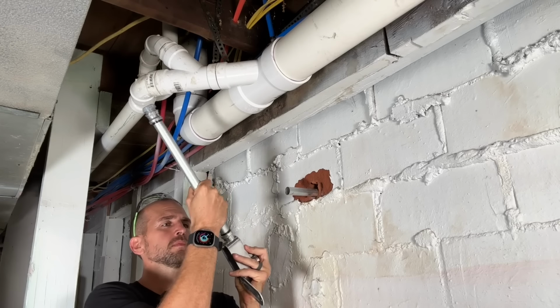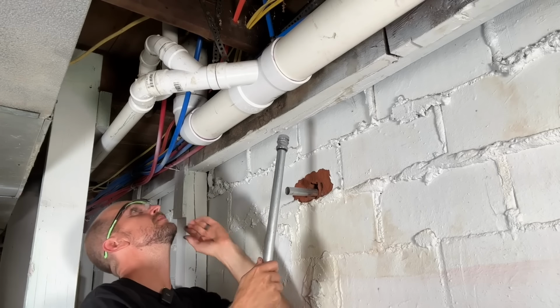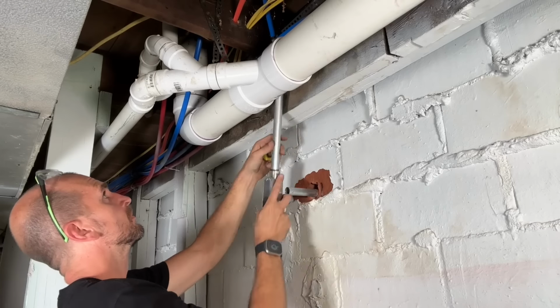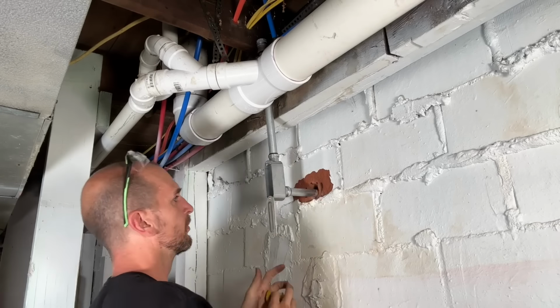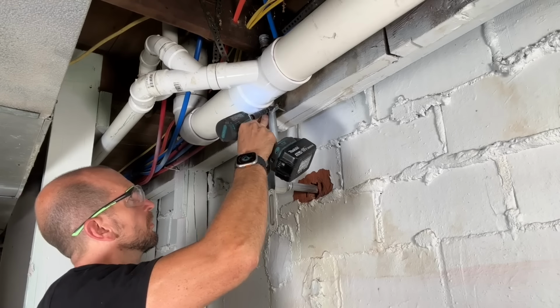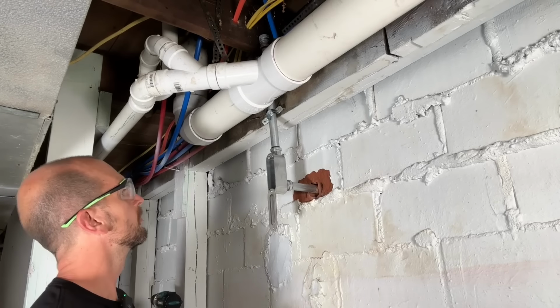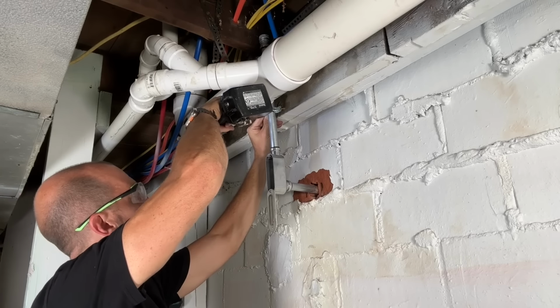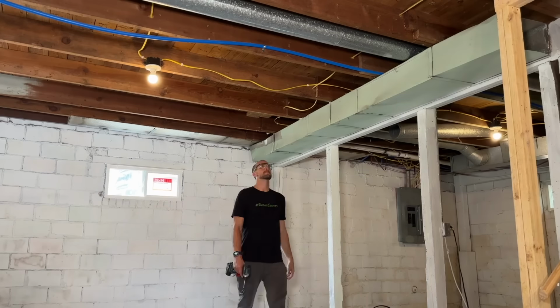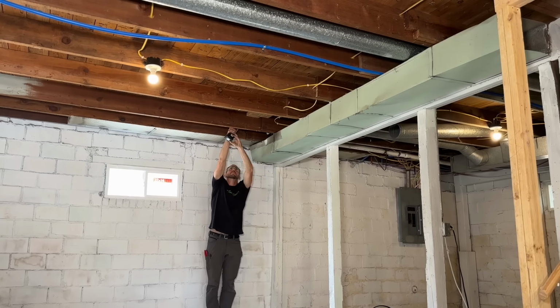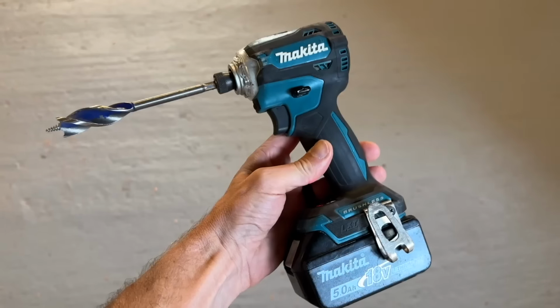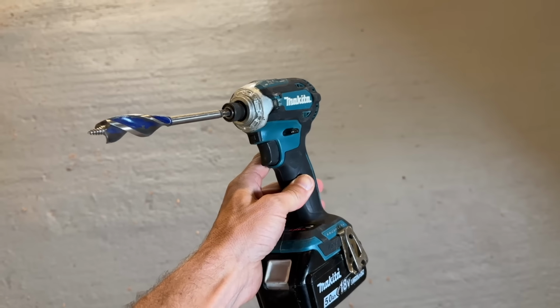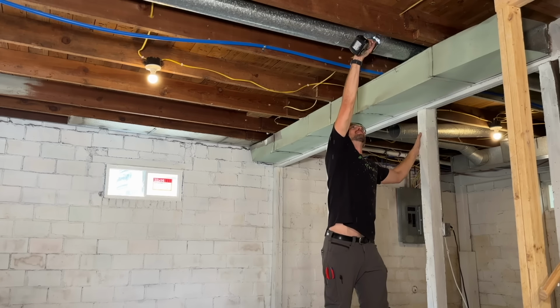And then we'll go ahead and get our 3/4 inch conduit with the LB body attached with the conduit going outside. This is going to give us a nice path to the outside disconnect box, and we'll secure this up prior to running our Romex. So for the Romex on this 50 amp circuit, it's going to be 6-2, that's 6 gauge 2 conductor with a 10 gauge ground. I'll be drilling holes with a 3/4 inch Irwin speed bit and my impact driver.